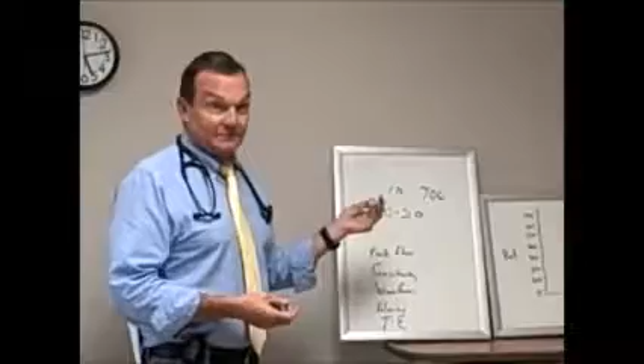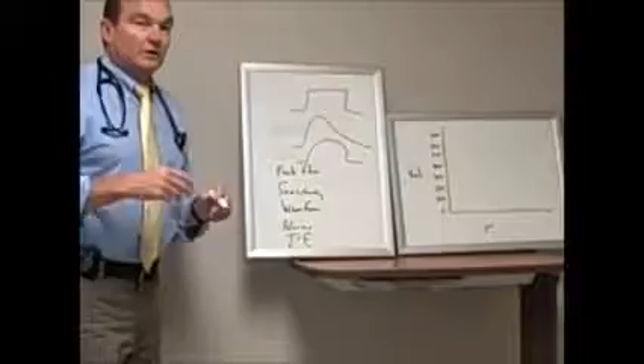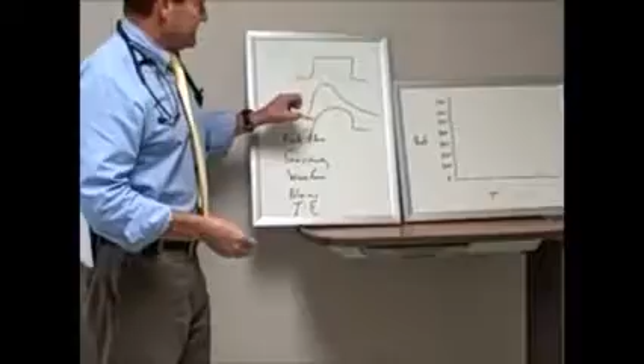So that's just something you got to make sure. The waveform is what that tidal volume will be delivered at. You have 3 choices on a ventilator. You have a square waveform, you have a taper waveform, and you have a sine waveform. Okay? If you don't specify, the taper waveform is what they'll set at. So most of it's delivered in the first 1 to 2 seconds, and then the flow tapers off. That's how you and I breathe. The sine waveform, there really is no need to ever use it.